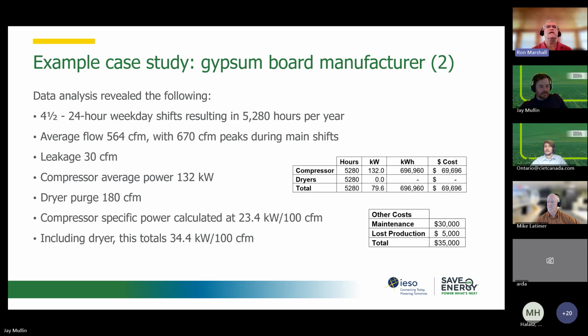Could you go back to that last slide? Yeah. So we were able to determine their weekday, right? They weren't operating 100% of the time, only 4.5 days per week. We could see the flow rates, the peaks, the leakage levels. We measured the power. We could see dryer purge was pretty significant and constant, even running outside of those production shifts, right?